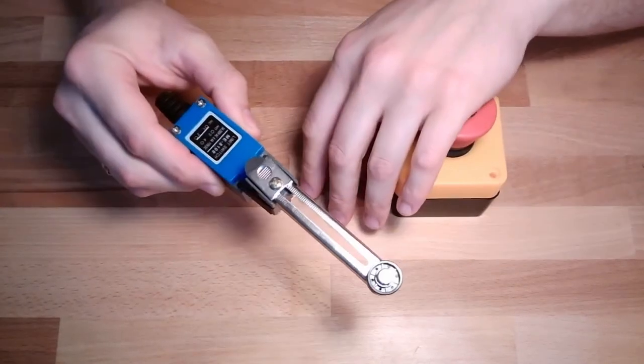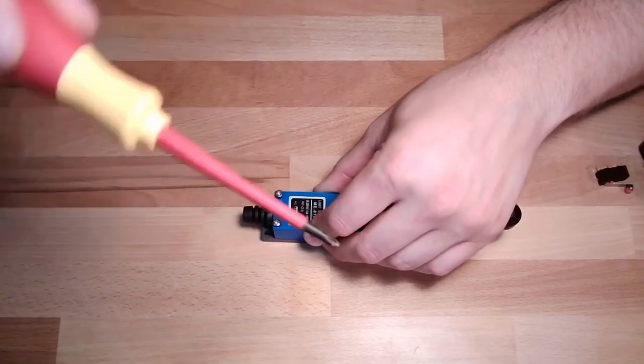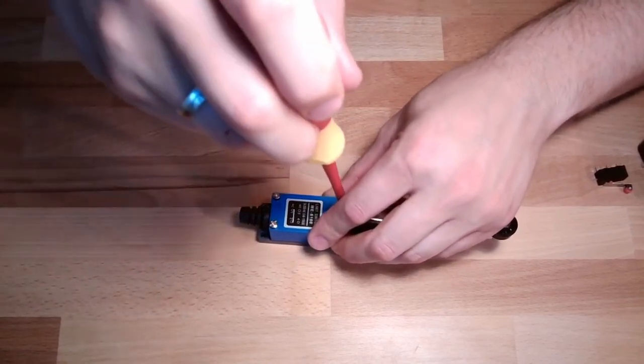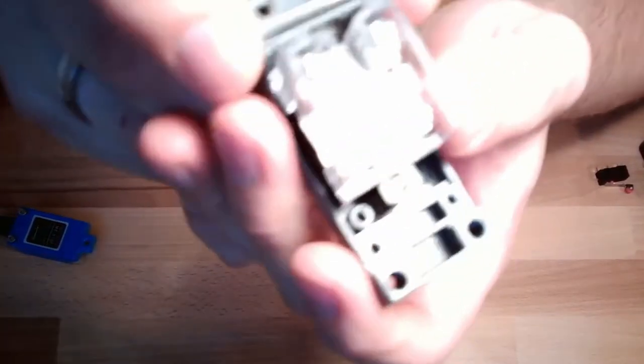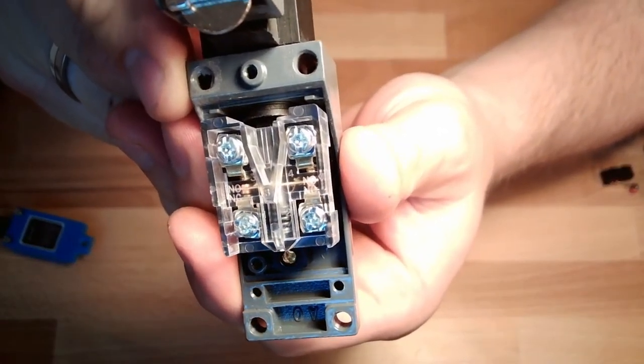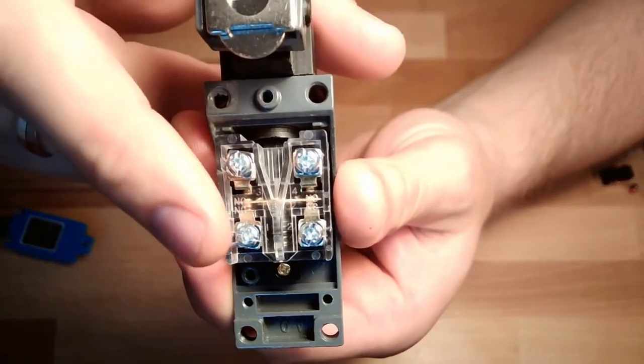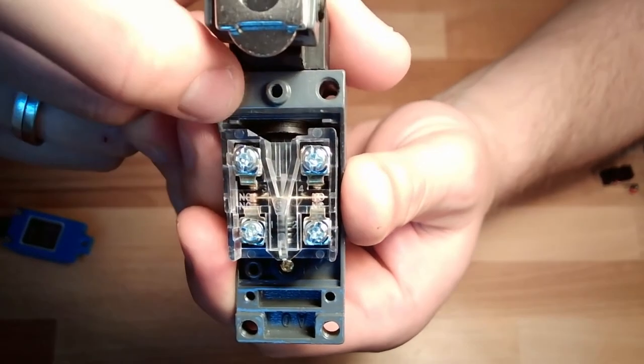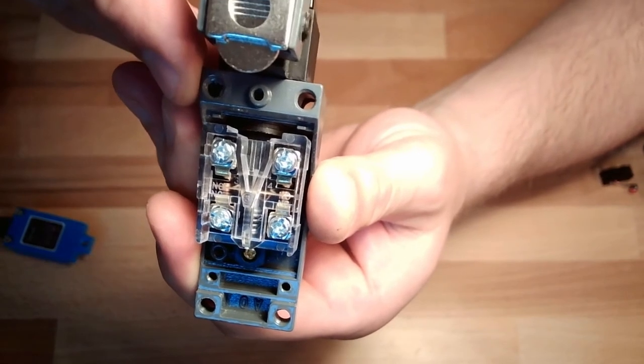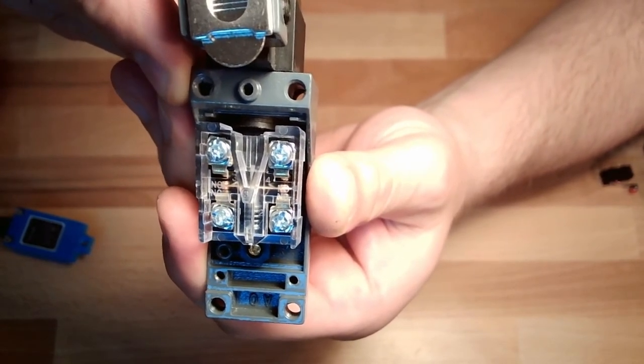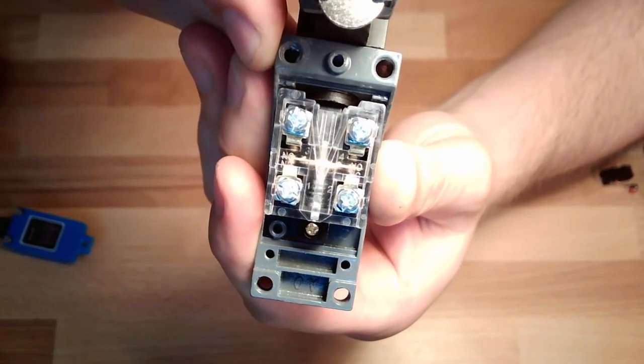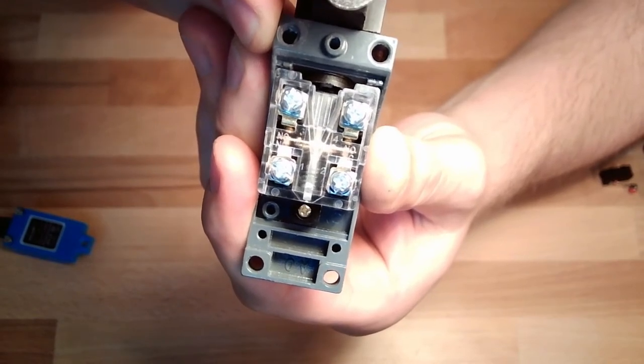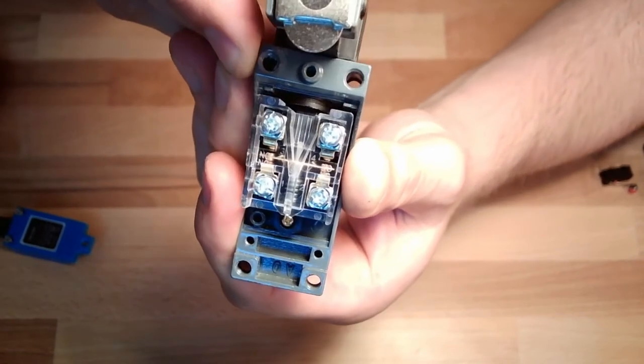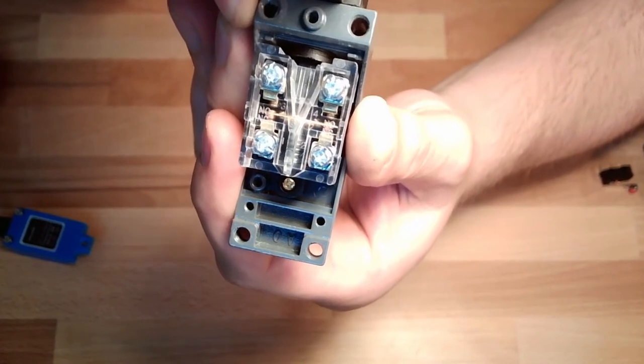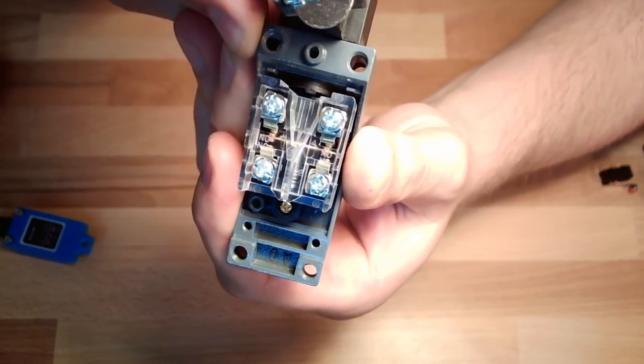Okay, I will open this one here now. It's really well screwed. Okay, here you see, right now, the contacts are connecting. Those two, the bottom screws and the upper screws, are not connected to each other. If I move it, you see, there is the contact which is springing, jumping from one position to the other. So this is spring loaded. This is exactly to prevent bouncing, so that it is not touching back here or back there.